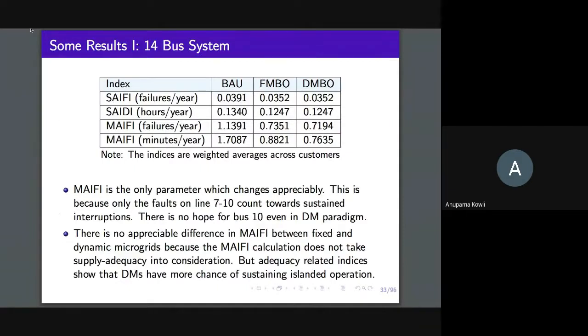We calculated what the reliability indices would be under the business as usual strategy, what they would be with predefined microgrid boundaries, and what they would be with dynamically adapted microgrid boundaries. You can note that if you have tie switches in the network, then mostly loads are going to face only a momentary interruption.